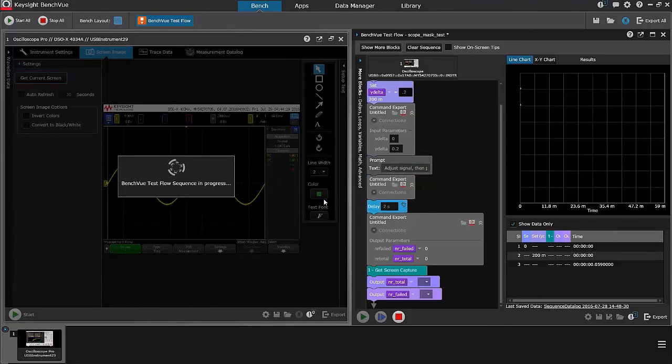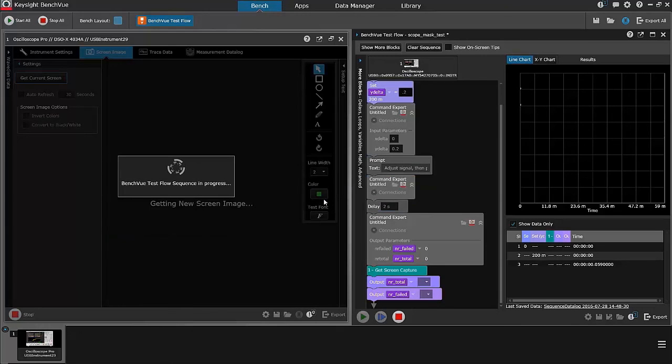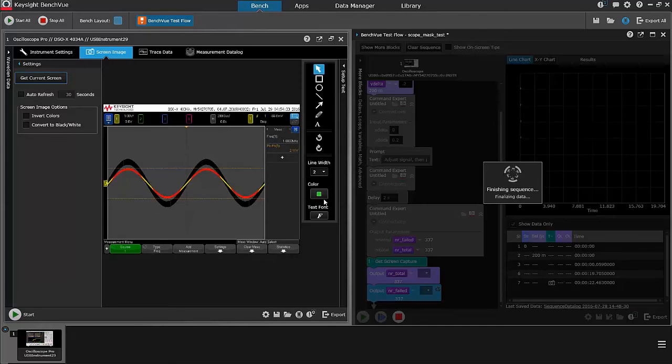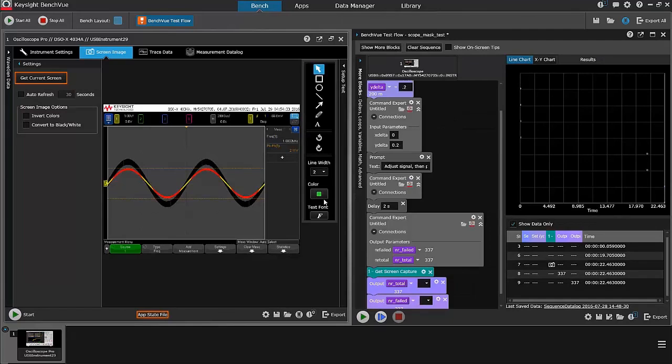When I do that, it's going to fail. So, the test will generate a waveform that is outside the limits set by the mask test.